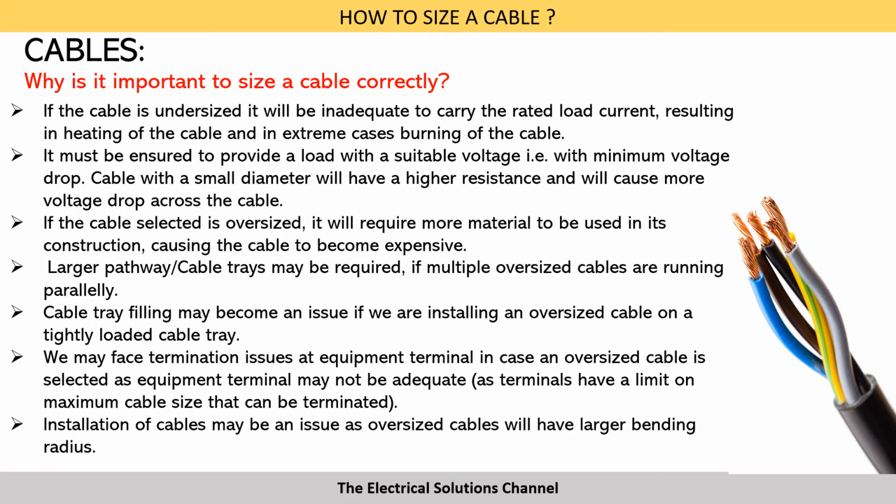On the other hand, if the cable is oversized, it will require more material to be used in its construction, causing the cable to be more expensive. Larger pathways or cable trays may be required if multiple oversized cables are running parallelly. Even the cable tray filling may become an issue if we are installing an oversized cable on an already tightly loaded cable tray.